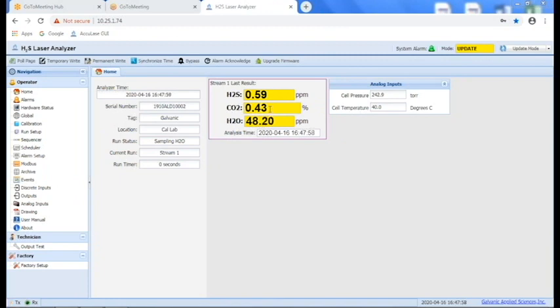We can do that for a fixed period of time, typically 10 or 20 seconds, and then it jumps down to CO2. To do that, it changed the drive current of the laser to put out a slightly different wavelength that corresponds to an absorbance feature of CO2. H2S and CO2 are very close together, so there is potential for them to interfere with each other, but we mitigate that by using the vacuum pump to narrow the lines. It allows us to measure both components with a single laser just by changing the wavelength, since the features are within tuning distance on a single laser.